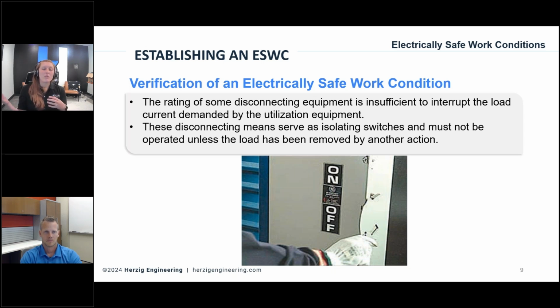So if it's still drawing power while you make or break a circuit, it could have some electrical arc over. And it's not a matter of if, but when you do that too much or there's too much current being drawn, it'll actually arc over enough that you could have that potential of an arc flash. It could ionize the air around it, it could cross phases, it could cause a whole lot of different problems there. So make sure you isolate that power first, you shut down that equipment first before you open it up to isolate with the disconnecting point.